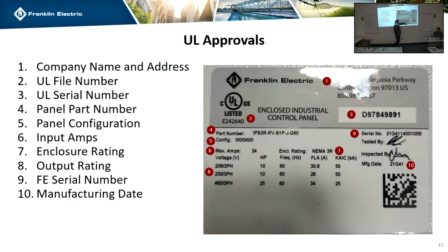Even if the enclosure itself says something like 4X, this is the rating of the panel. We can use different enclosures in different combinations to get NEMA ratings, so this is the one that you need to pay attention to. And then they will all have hand signatures of the people that tested it and inspected it.